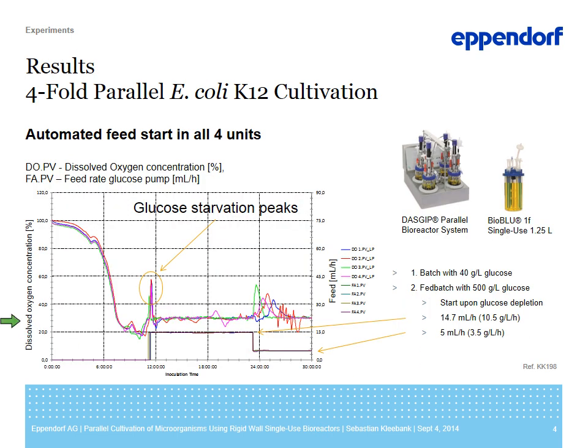Here on this screen you see the results of the 4-fold parallel cultivation. On the left side of the graph you see the dissolved oxygen concentration, and on the right side you see the feeding pump of our glucose pump. So after inoculation the dissolved oxygen concentration dropped from 100% down to approximately 20, in parallel in all 4 bioreactors. This happened due to the growth of the organisms and the increased metabolic activity.